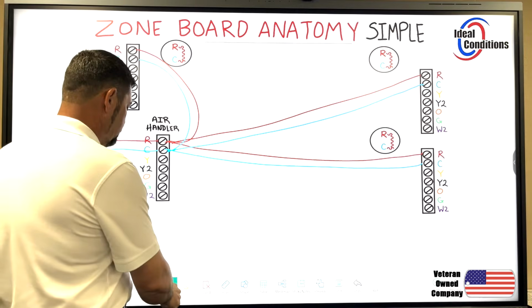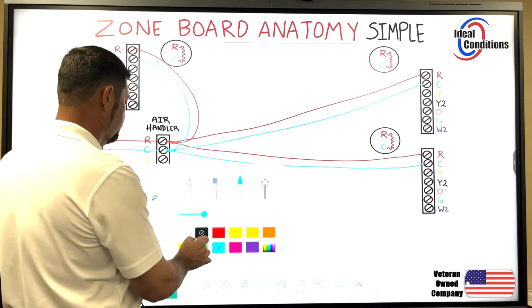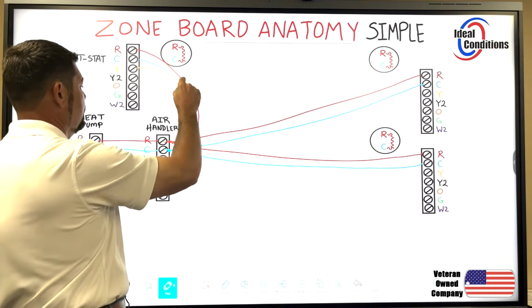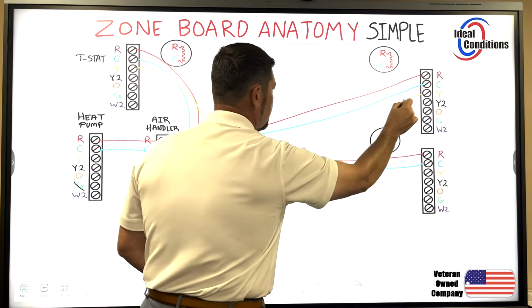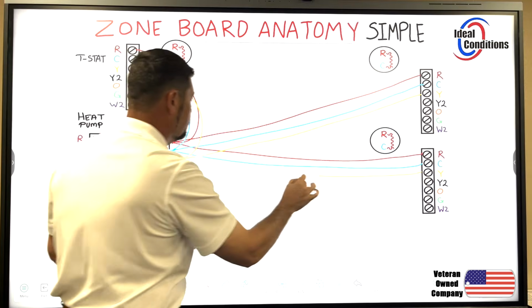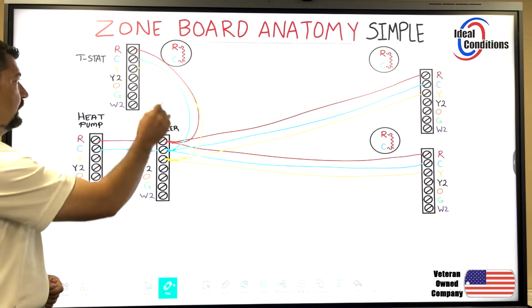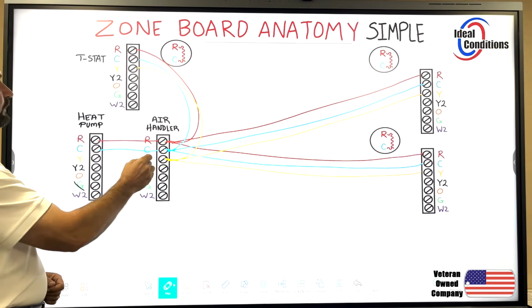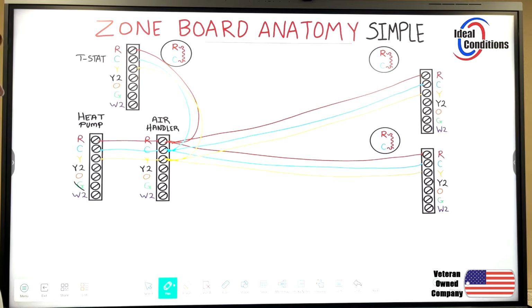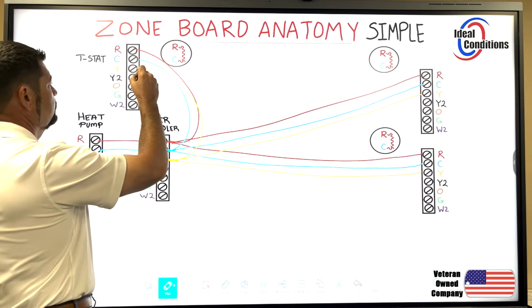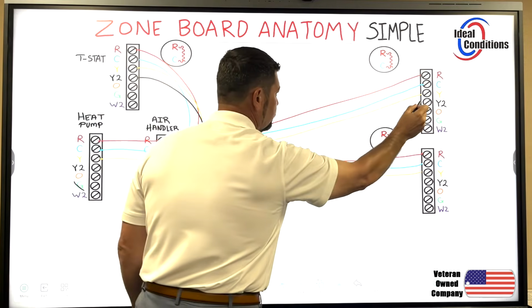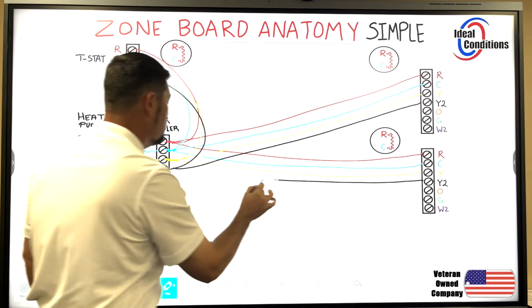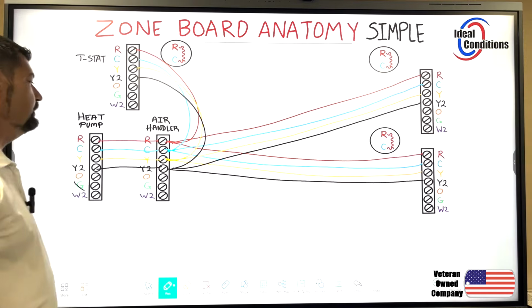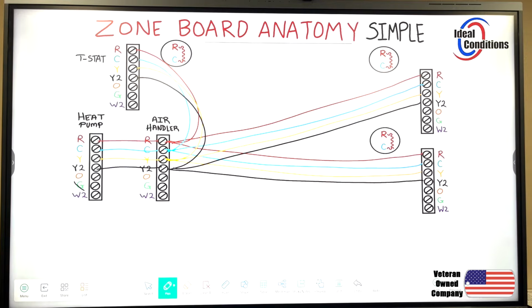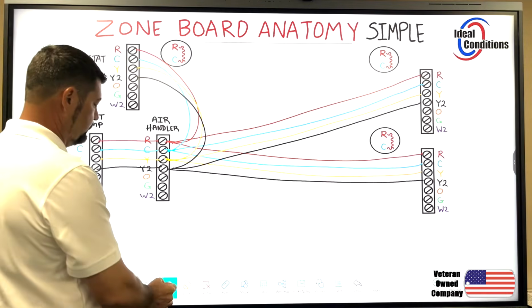Let's take it a step further, and let's start wiring up our Y calls. So this Y will come over here. This Y call will come over here. This Y call is going to come over here. They're all going to be in parallel at this point. So any one of these thermostats can call to bring on this air handler and condenser on a Y call. Right? Let's take a Y2. Let's energize the air handler from all the thermostats, Y2, and then we'll take Y2 directly to the heat pump. Any one of these thermostats can call for low speed or high speed compressor.